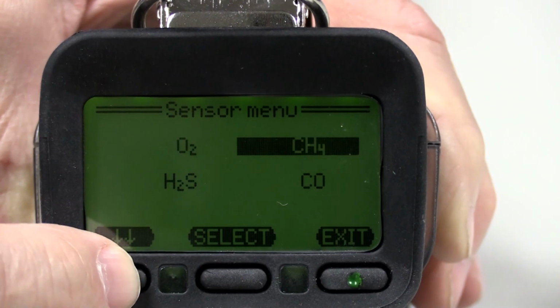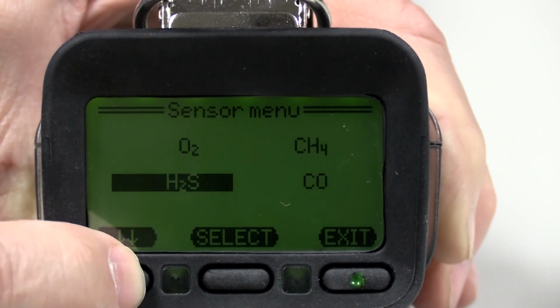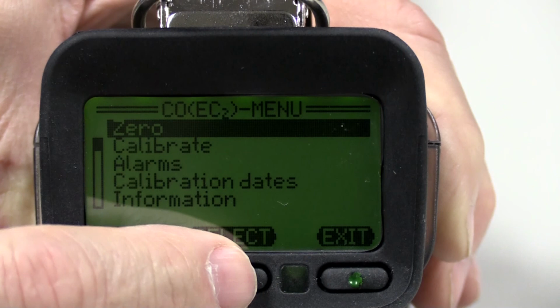The display will show the sensors currently installed in the instrument. Use the arrow button to select the sensor you need to calibrate, then press Select. The symbol for the combustible sensor is indicated by the gas used to calibrate the sensor. If the calibration gas is methane, the display will show CH4 for the LEL sensor. Once you select a specific sensor, you will have a list of choices. To perform a fresh air calibration adjustment, choose the Zero choice. To perform a gas calibration, choose Calibrate.